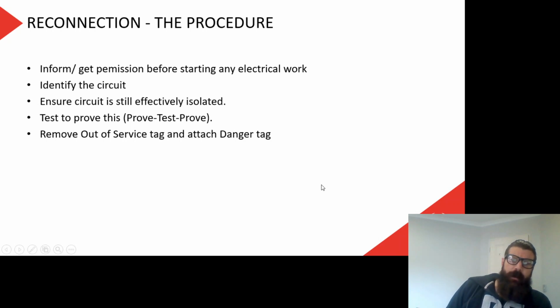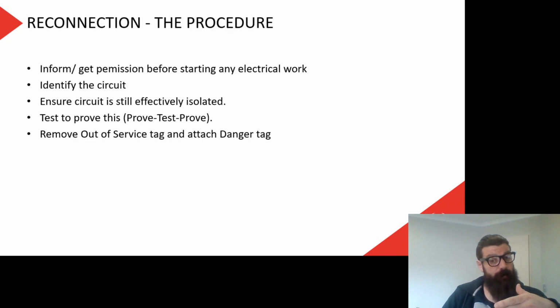So our reconnection procedure is essentially the reverse of our disconnection. First we talk to the person on site who's in charge, and we identify the circuit again. It should be the same one, but if you've left the site, go through that process of checking again, because you don't know what's happened while you weren't there. Ensure the circuit is still effectively isolated. If we left it isolated, then we just test it again using the prove, test, prove method. If we turned that circuit back on, if we relivened it when we finished previously, then we're obviously going to have to turn it off again.